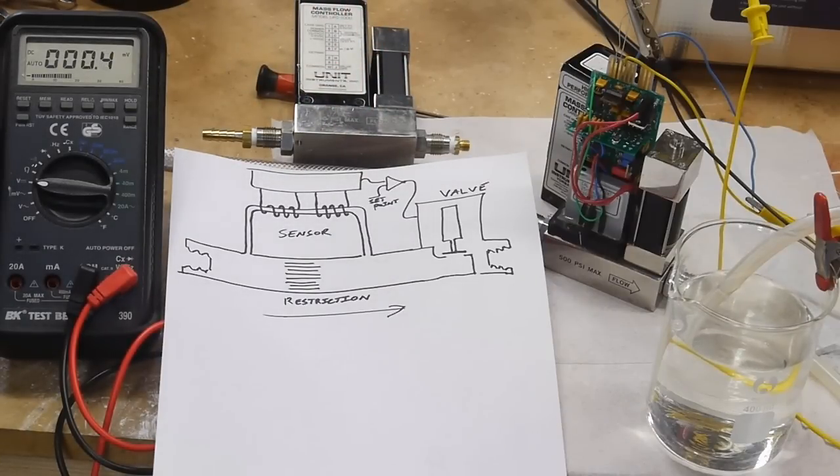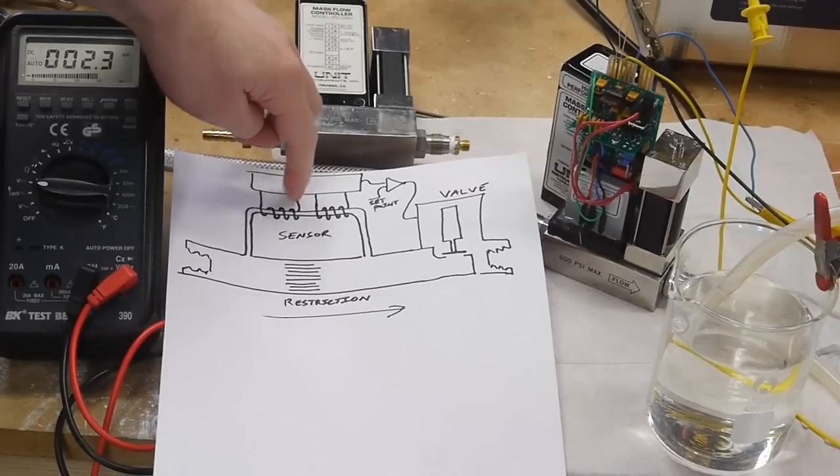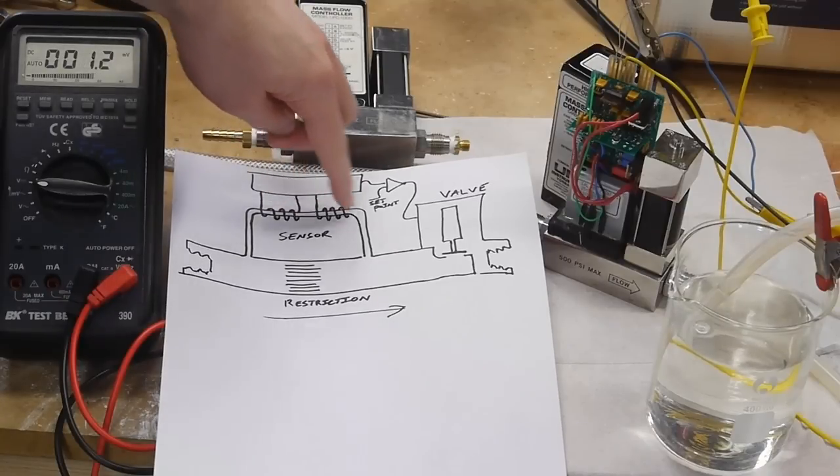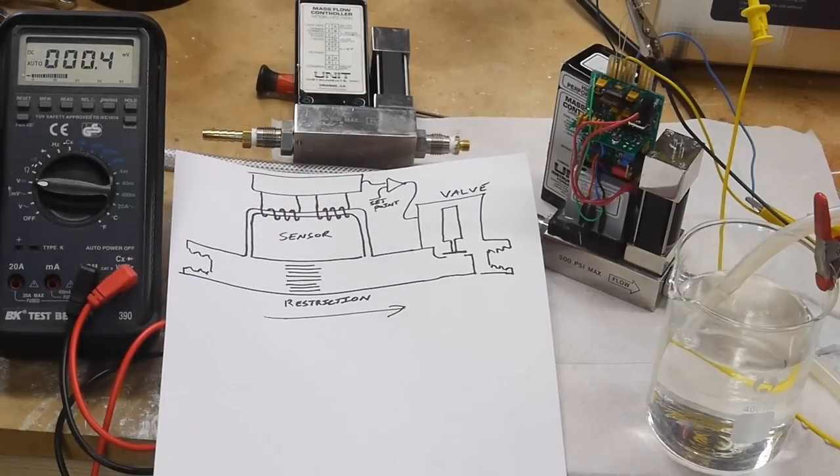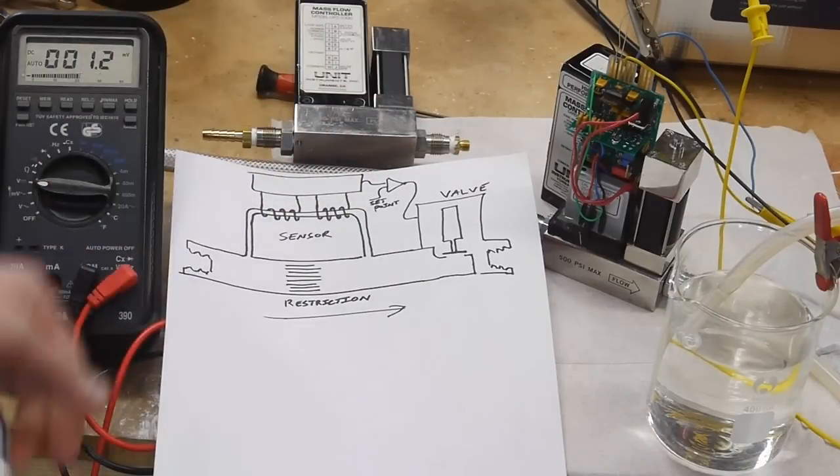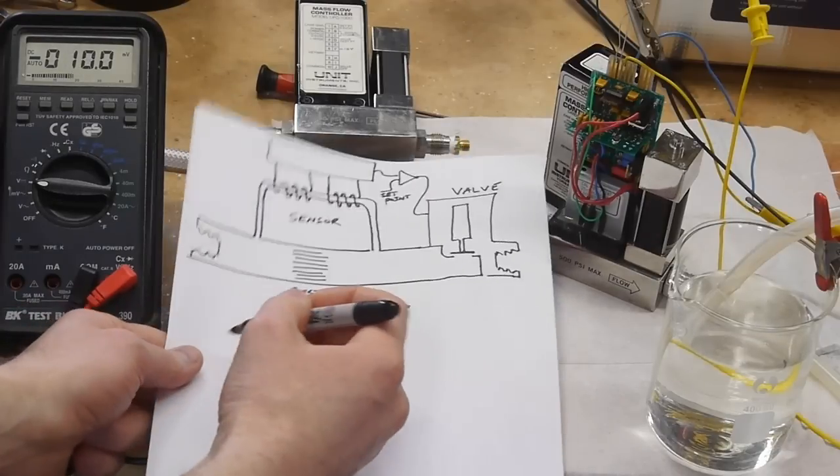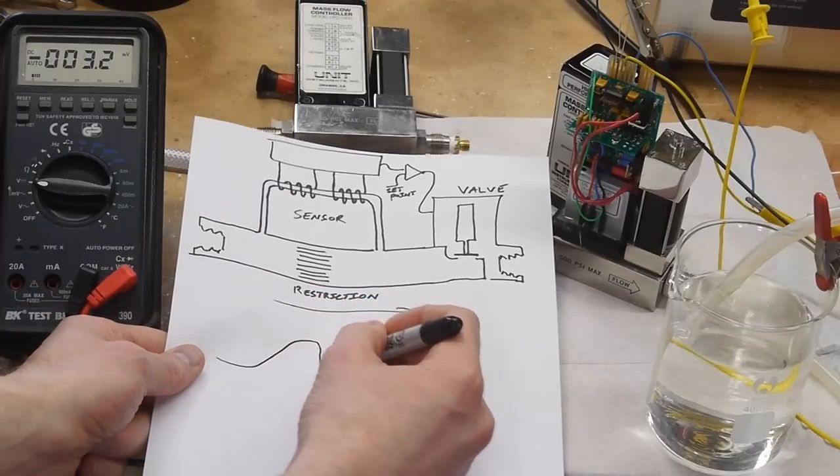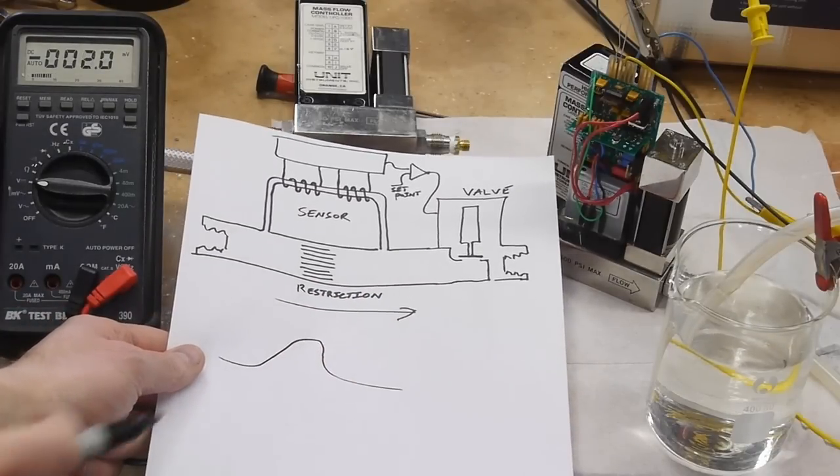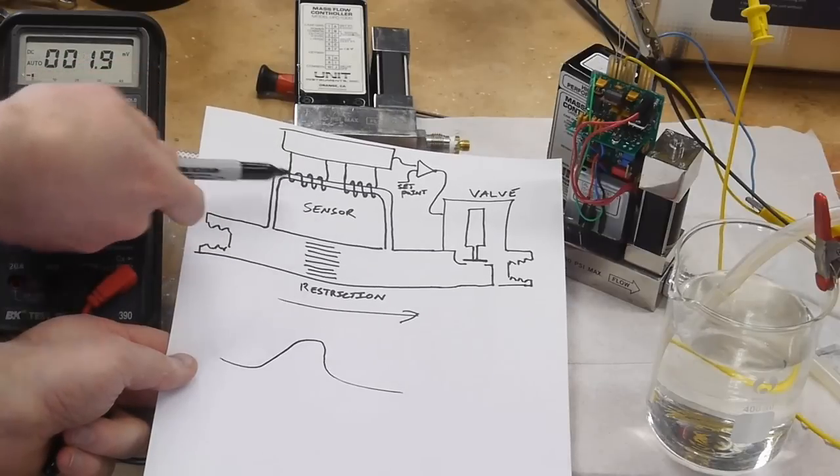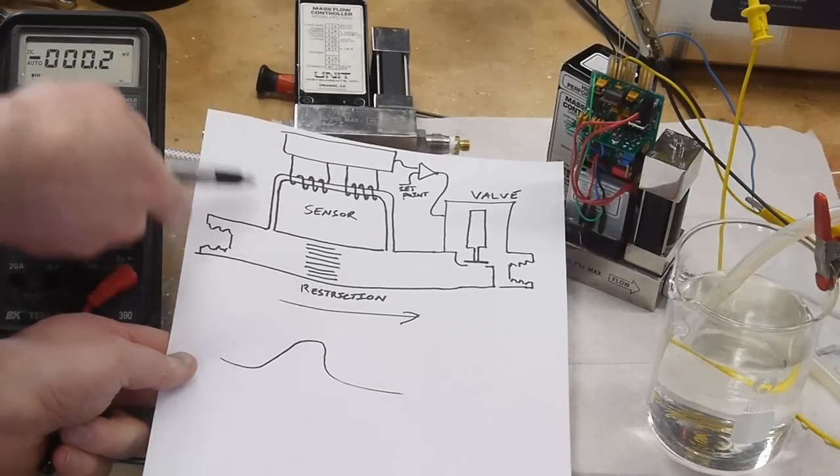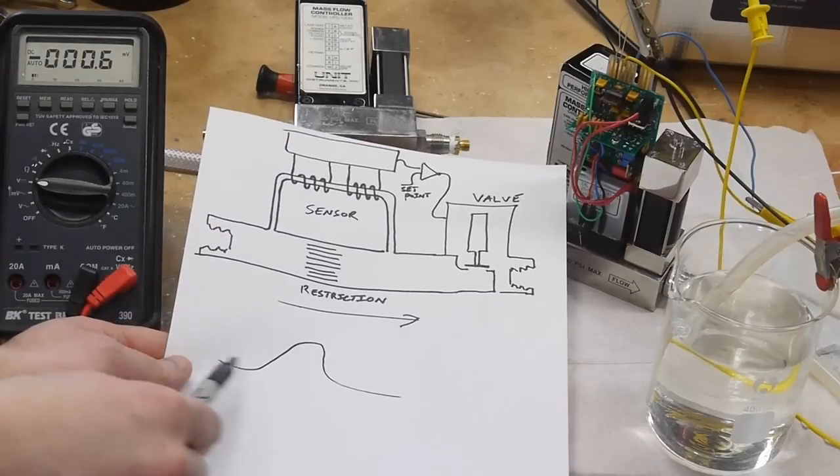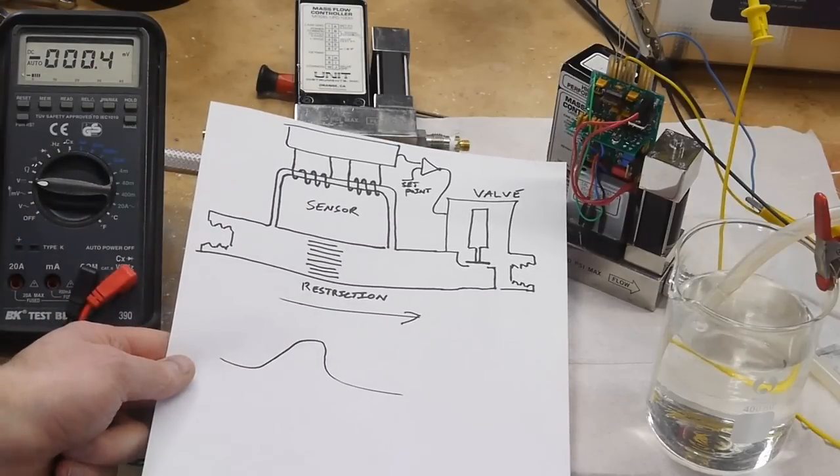So the way it actually measures gas flow is by applying a little bit of heat to this sensing tube here and normally if no gas were flowing through this sensor tube the thermal profile would look something like this. So the tube is hot here and it's not as hot at the ends because it's attached to the rest of the system so there would be this nice smooth Gaussian profile distribution.